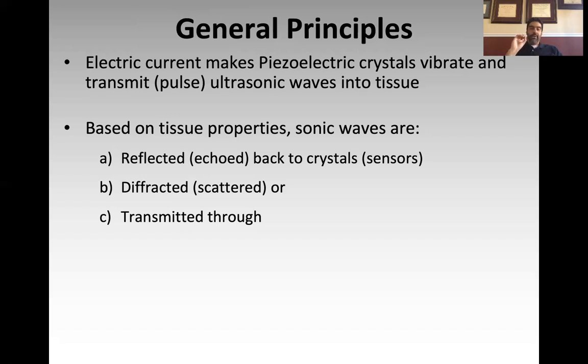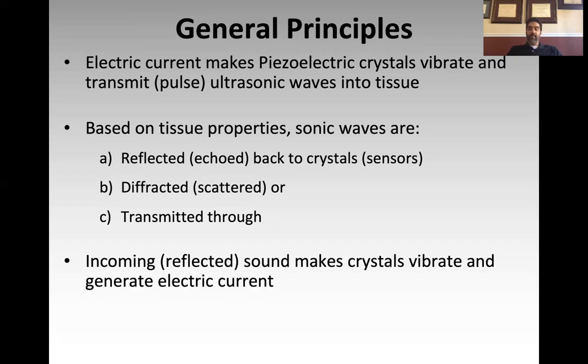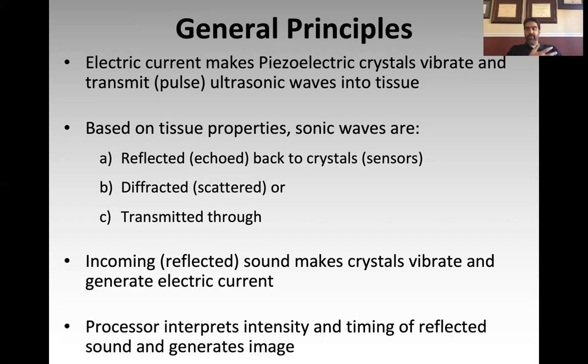The sound is either reflected back, scattered, or transmitted through. When the sound is reflected back, it hits the crystals, makes them vibrate, which generates an electrical current. That electrical current is pushed back into the machine, and then the fancy processor inside interprets the intensity and timing of the electrical current and generates an image based on those properties.